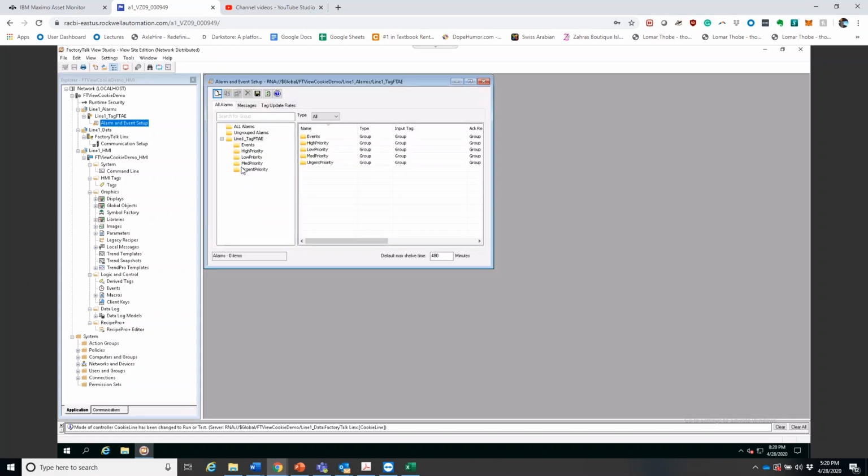If you notice, we have some high priority. We have alarm 4, 5, 6. These pretty much, you notice we have 3 digital alarms and 1 level alarm. Alarm grouping attribute allows a user to logically group alarms and then use the alarm summary object to filter by pre-configured groups of alarms. In our case, alarms have been pre-arranged in groups according to their priorities.